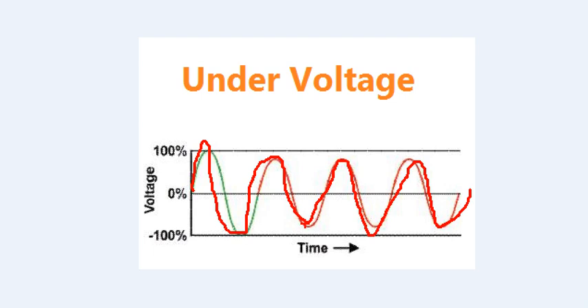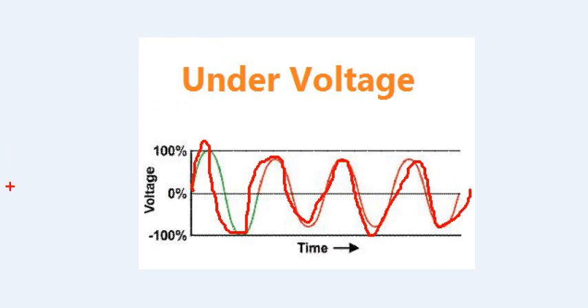In the first stage, there are many settings. The first stage is set at 90% of the minimum line voltage. In the second stage, there is 85% of the rated voltage setting.